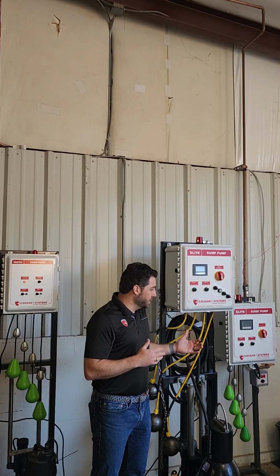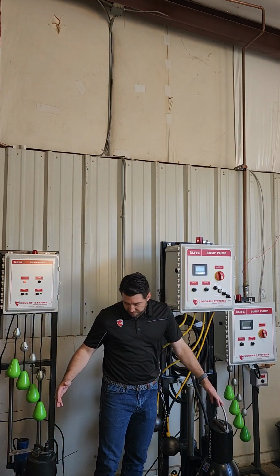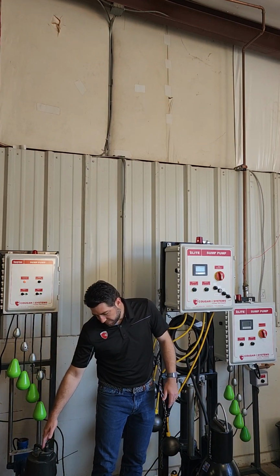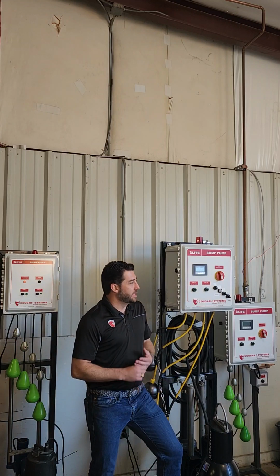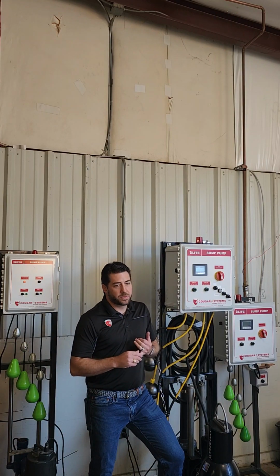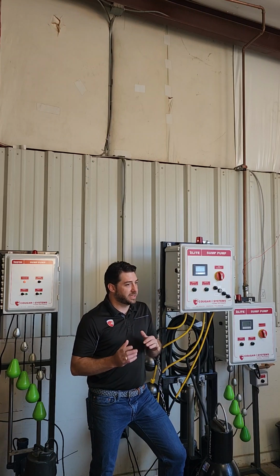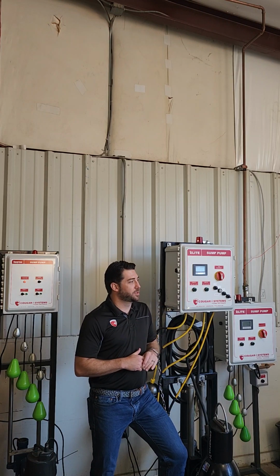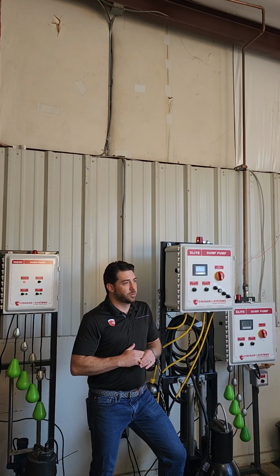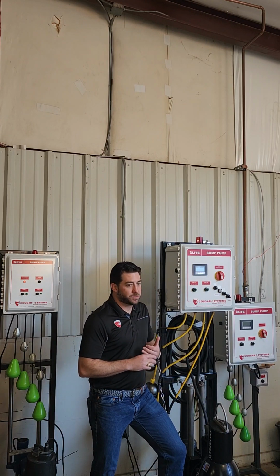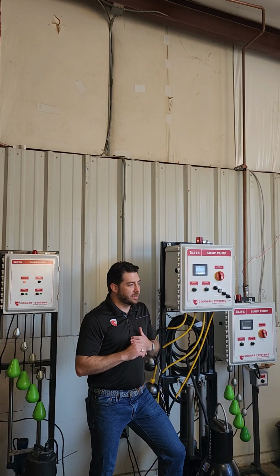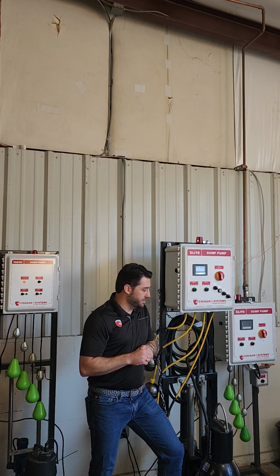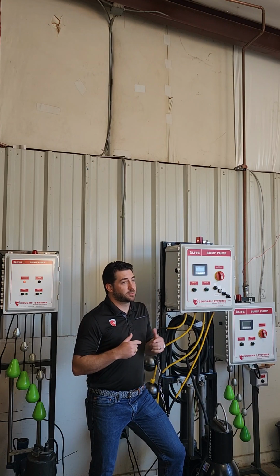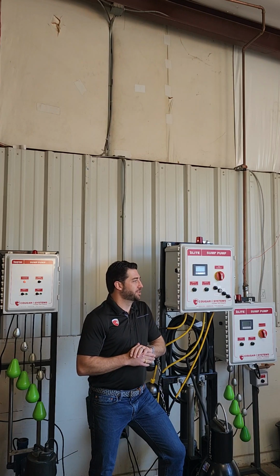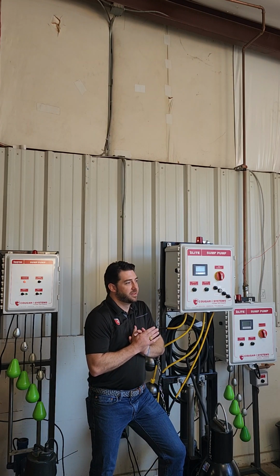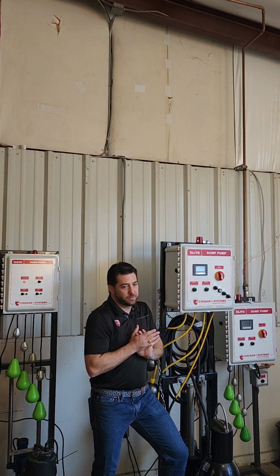So really the only difference for us in terms of storm or sanitary, like either one of these pumps can be used in either one, is how we're going to typically do the floats. On a sanitary pit, we really want to have fewer floats so that we get to that high level alarm faster. And we'll talk a little bit more about that when we talk about the float switches. And then we want to make sure that those systems are serviced regularly, right? That you guys are in there making sure those pumps are working, because we definitely don't want to have high level alarm issues with a sanitary pit.